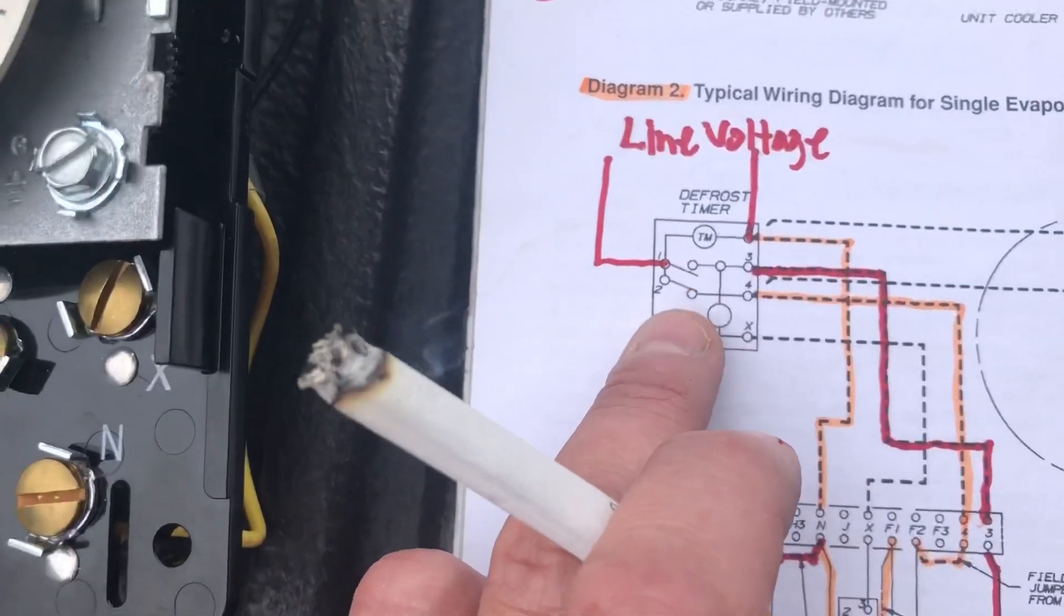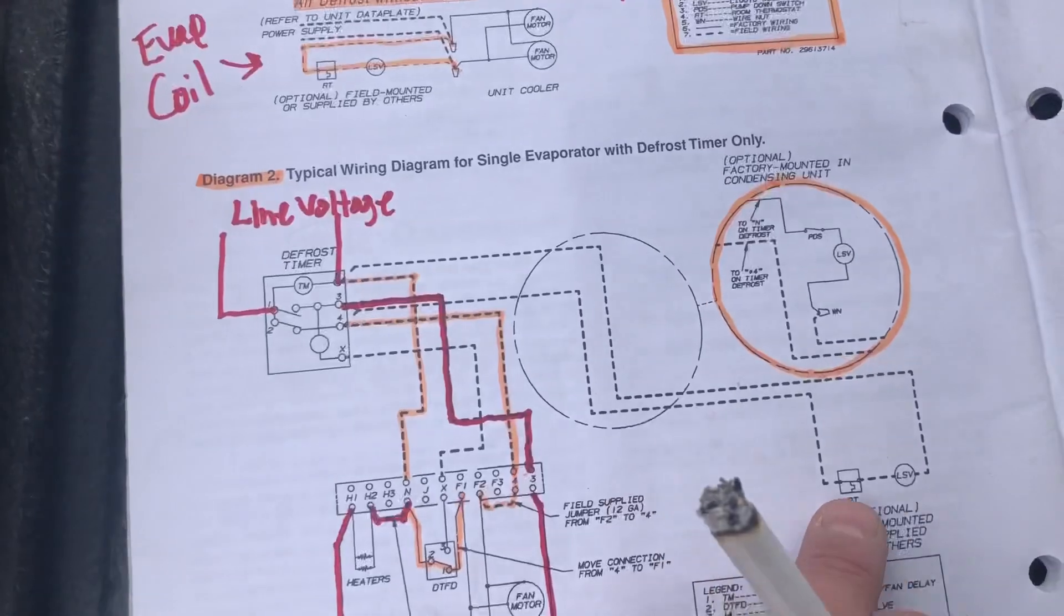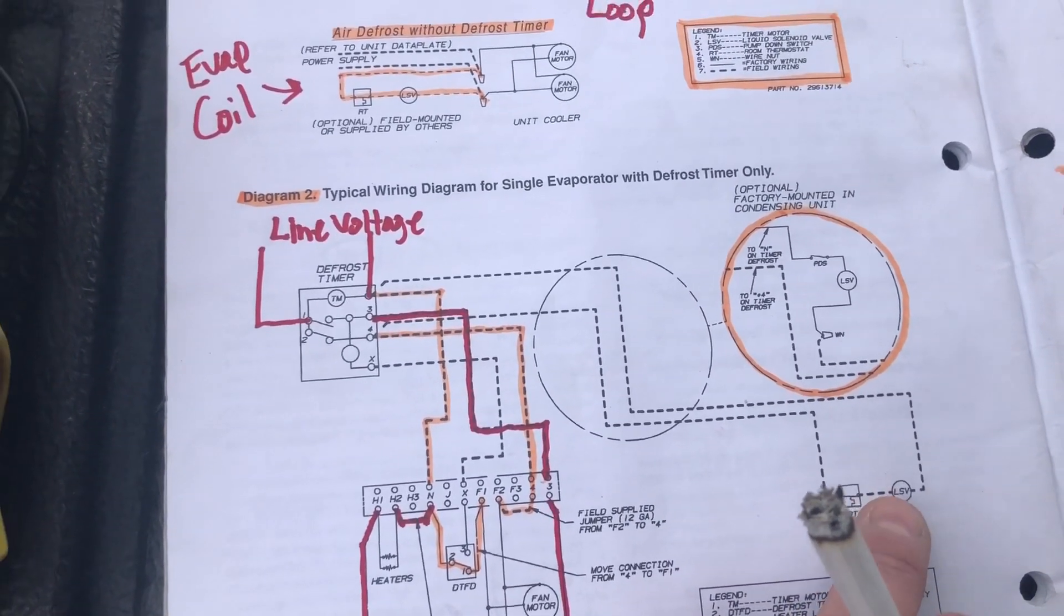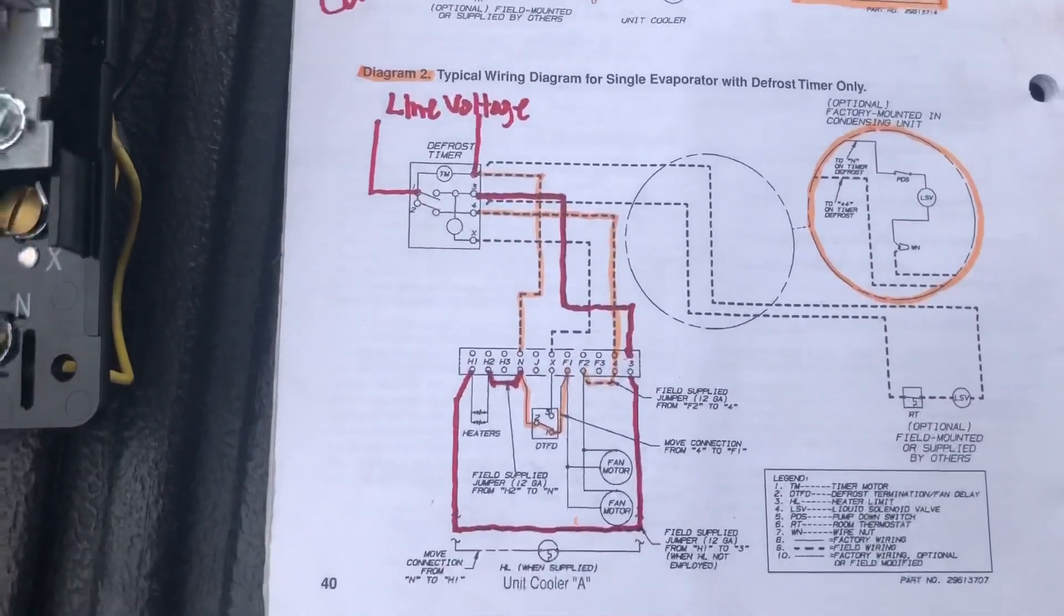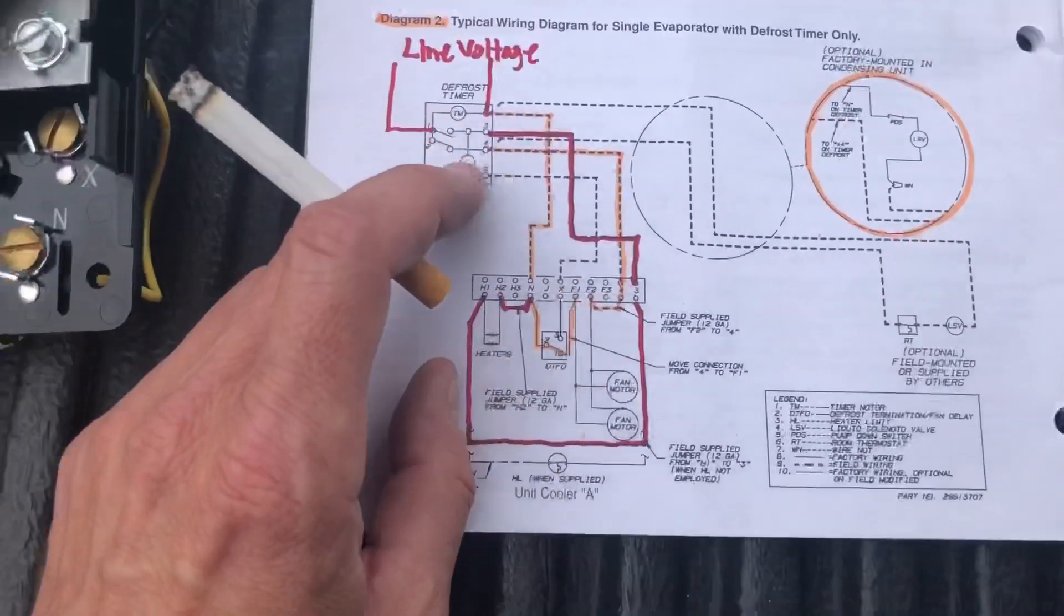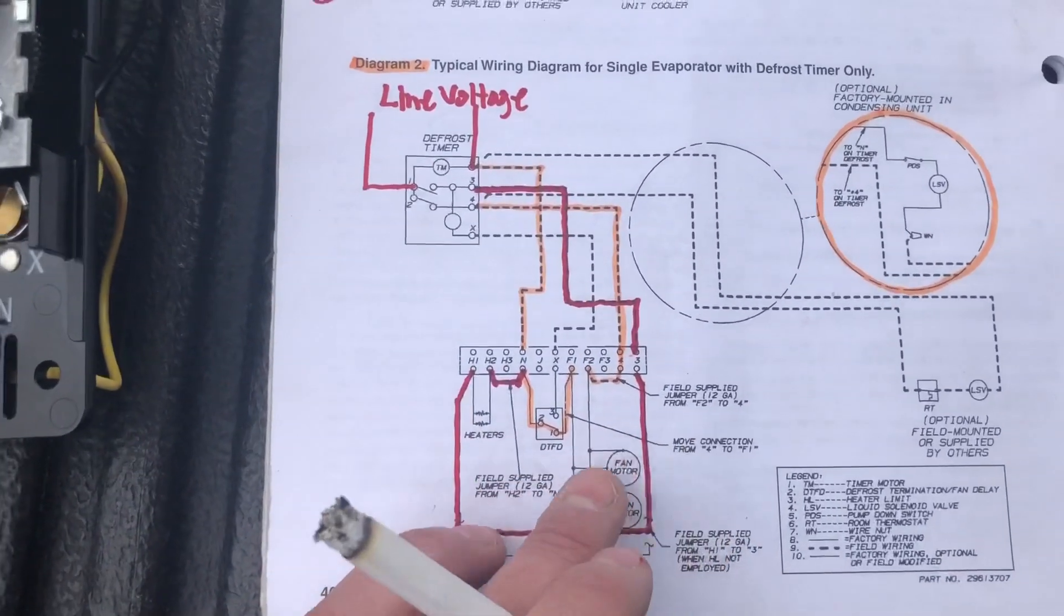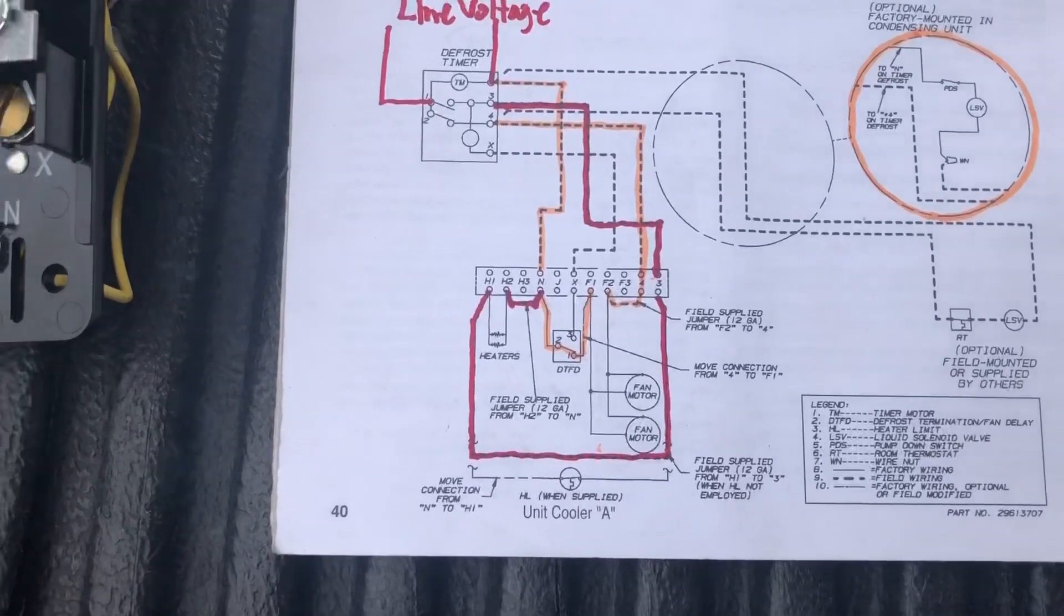I also want to mention in the defrost cycle, because we stopped bringing power to 4, you can also see it goes over to our control loop, that opens up the power for your thermostat and your solenoid. So the solenoid shuts down, pumps your system down, gets all your refrigerant back into your receiver. And then the heaters will power, your fans will shut off on your coil so the heaters can run.